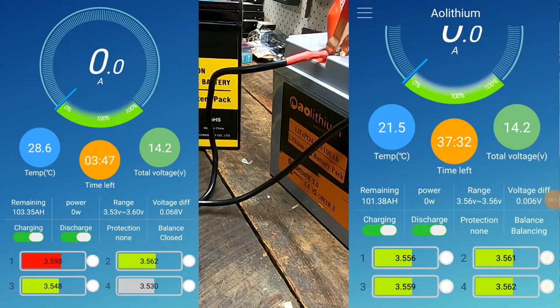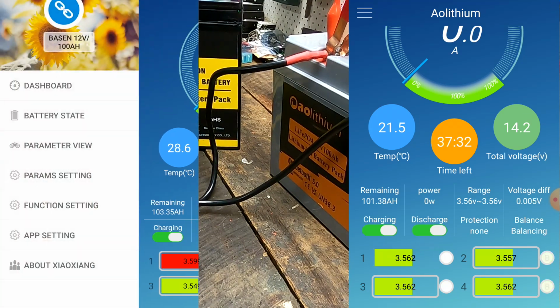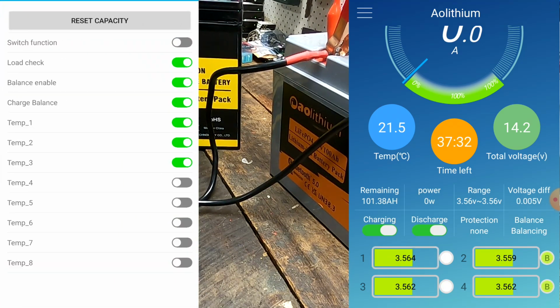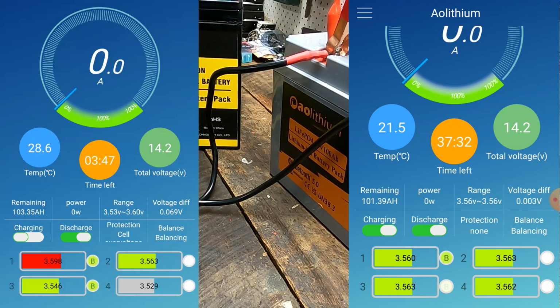You also need to give your BMS a bit of time to actually balance your battery at, say, 14.2 volts, which is 3.55. So what I want to do now is we are at 69, 70, 71 millivolt deviation in the Basen. We go into the function settings and turn on charge balance, and you can see the BMS is starting balancing right away.